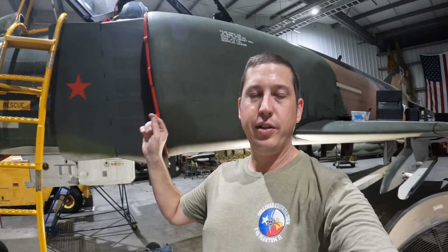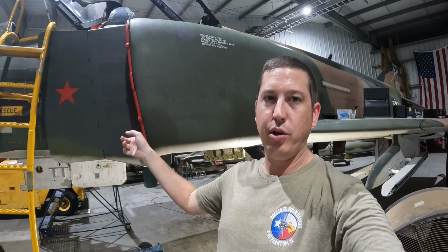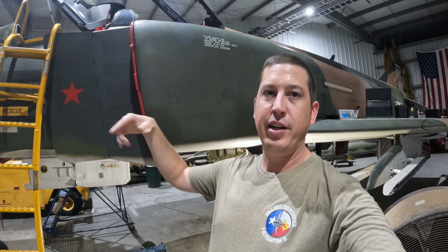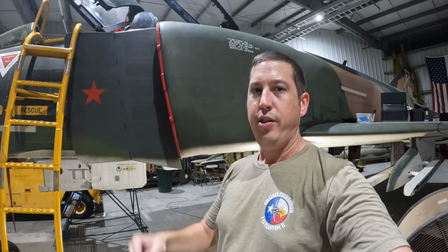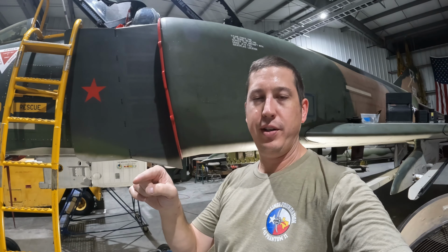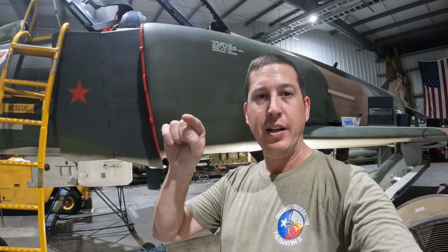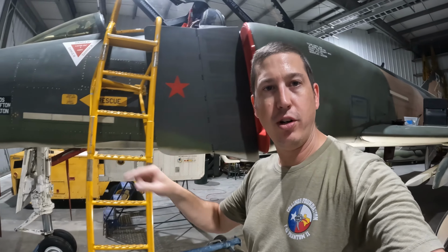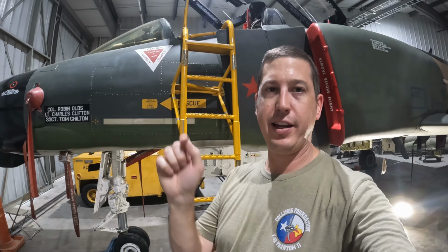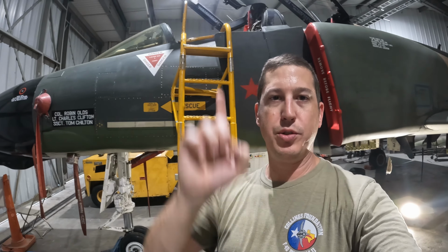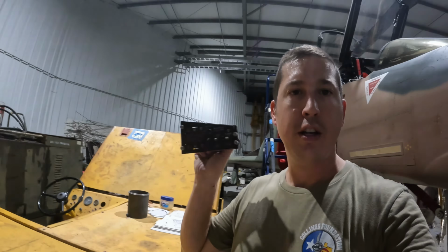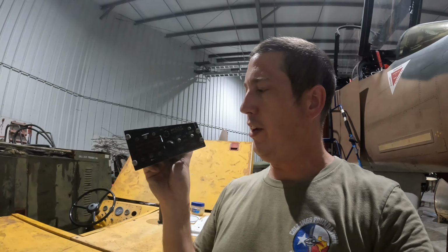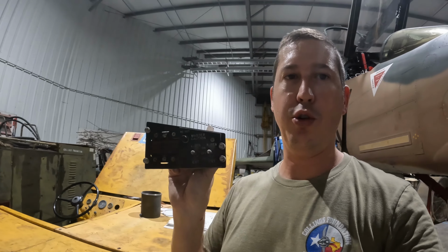So a little bit of electrical power is tapped off of the plug, goes to that power supply, and makes 28 volts. That 28 volts goes down to pin E on the plug. Inside the actual plug is a loop that connects E to F, and that goes back up into the jet and then ends up at, where's my panel? So that 28 volts ends up here at the generator control panel.